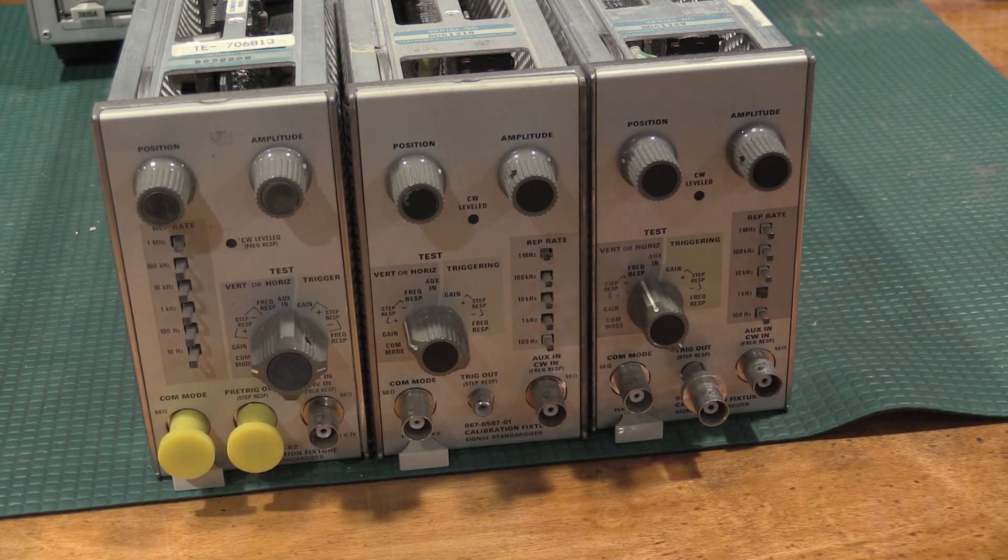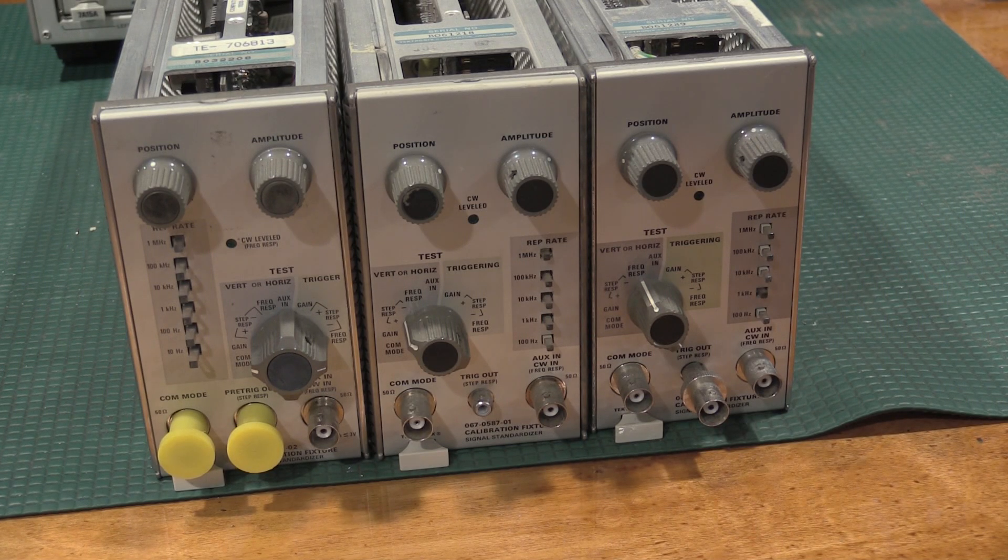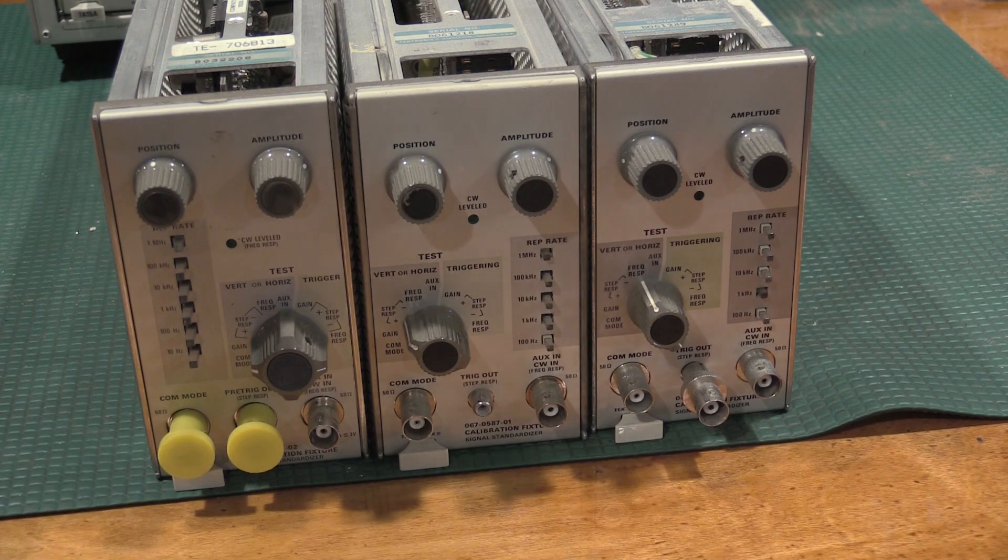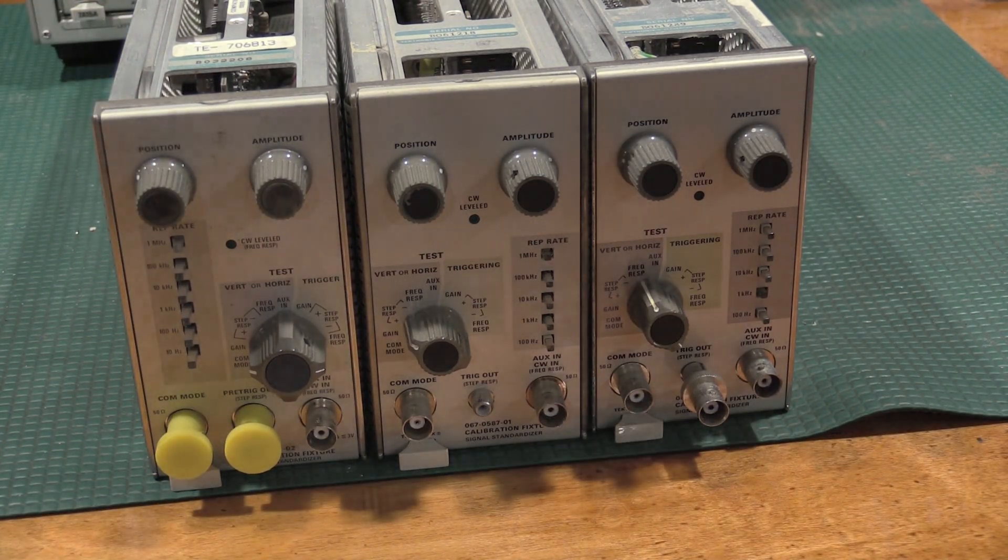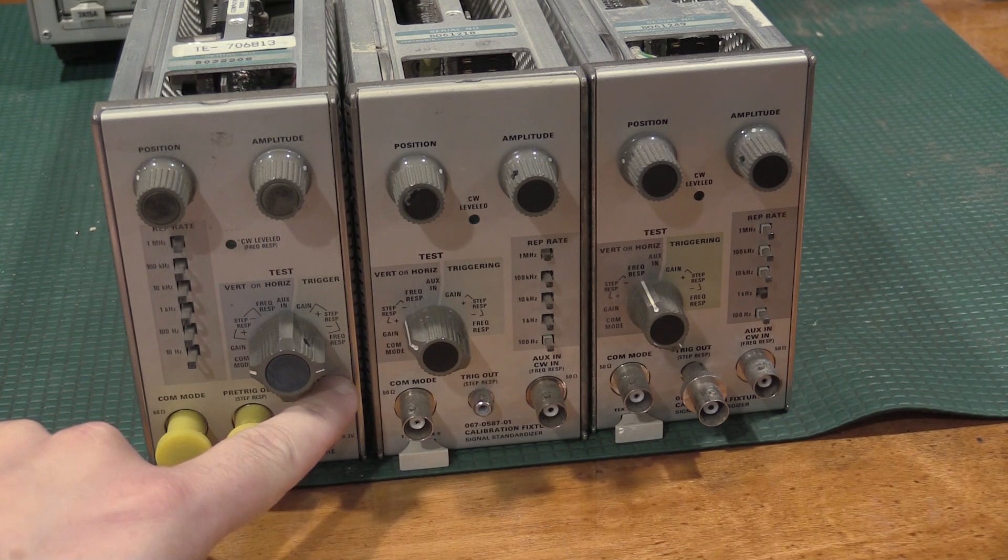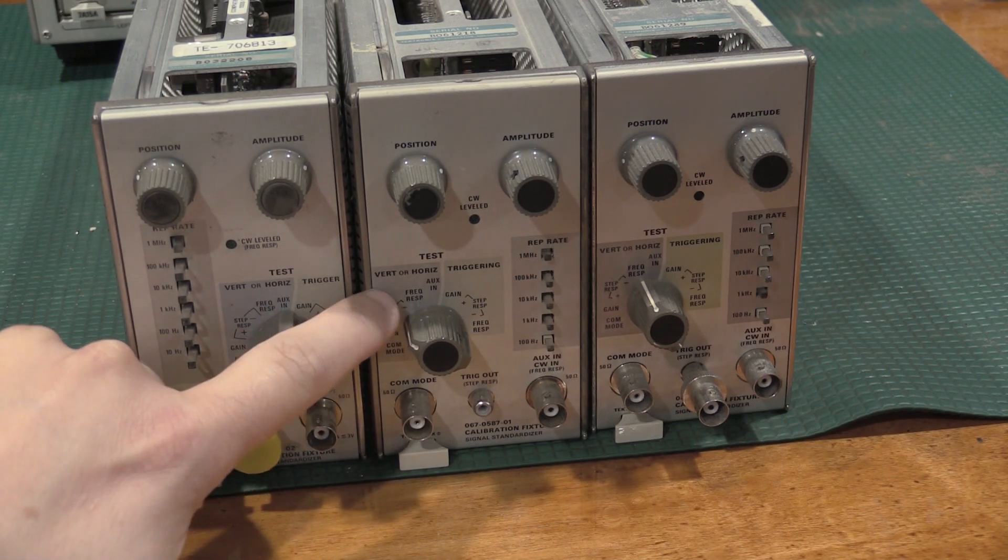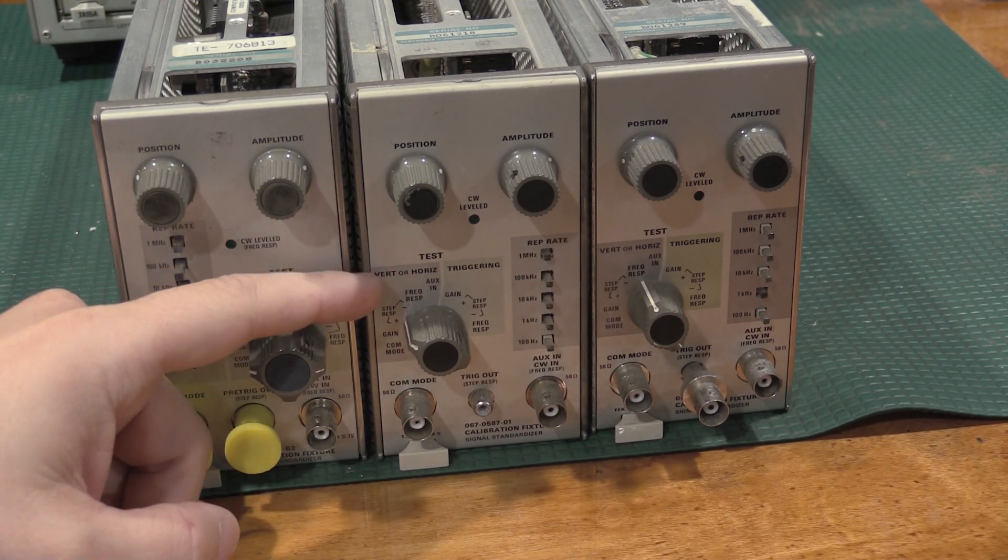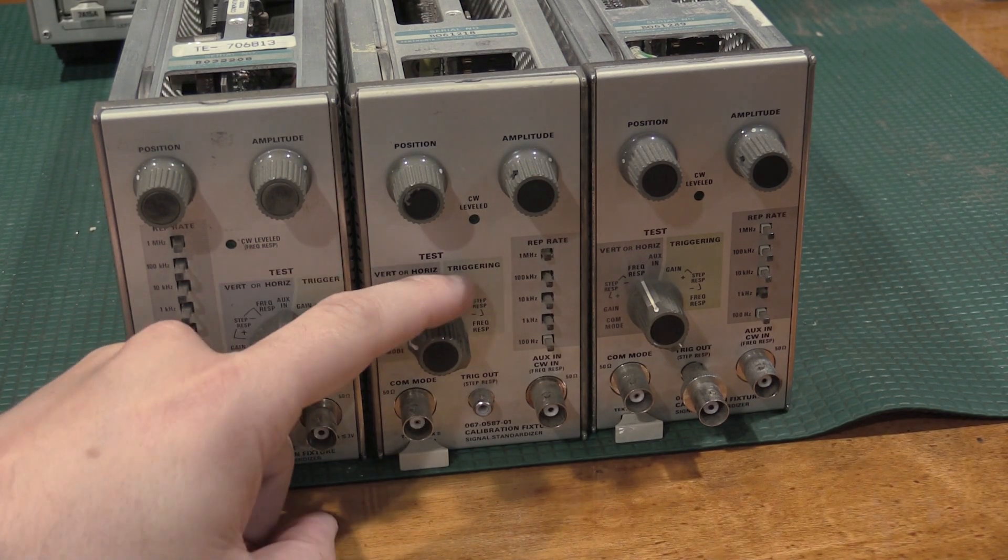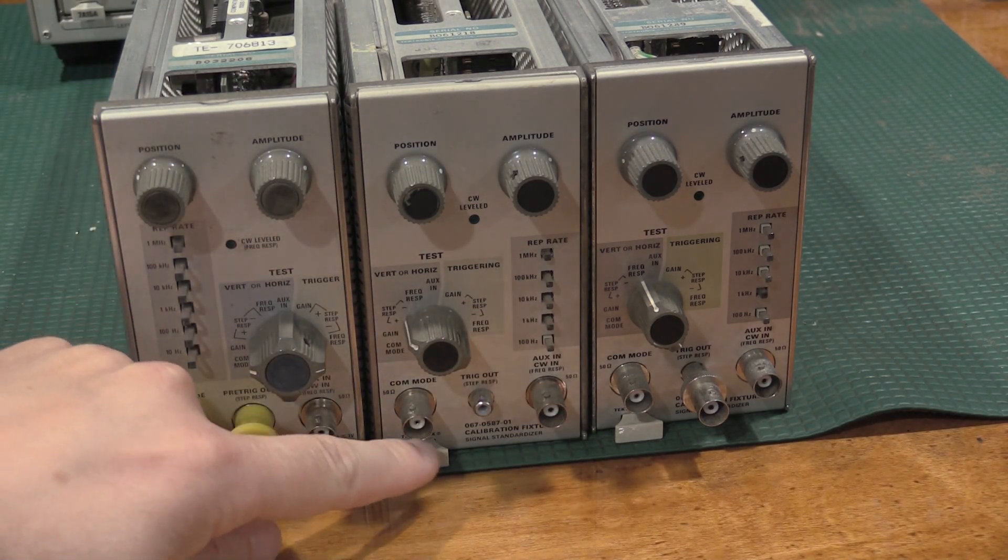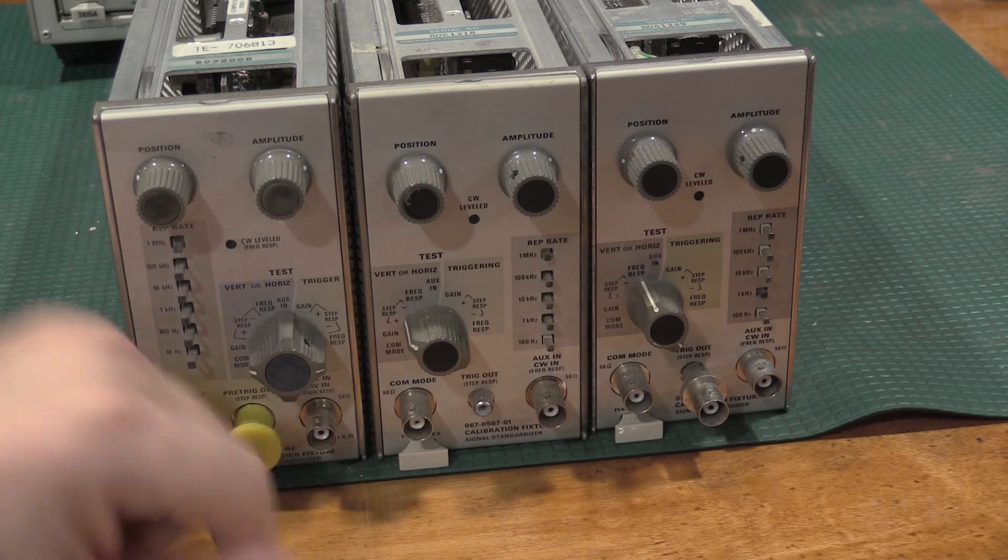Every once in a while, you can catch these on the secondary market. They are not inexpensive, but there's not a lot that goes wrong with them either. They kind of either work or they don't. They have the typical cam switch disease and a few other things. This one in particular, you have to be really careful with, and I'll get into that here in a little bit too, when we take a look at some of these. But as you can see, so it has a common mode. Then we have some gain. We have vertical or horizontal step responses. These are used very often in the alignment of the bays because you're essentially peaking the response of the individual sockets. But then this also does some triggering response and things like that too.